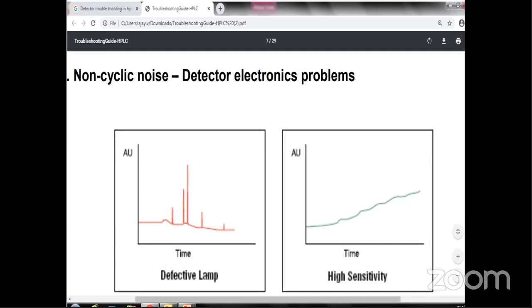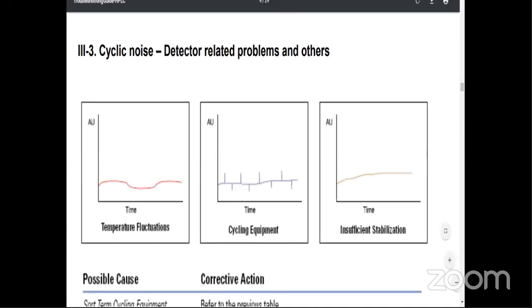And with high sensitivity, you can see there is a drift in the system showing up. If you're using a very highly sensitive detector, which makers are now providing, you may never have faced such challenges in other makes of HPLC, but particularly in these upcoming HPLCs you'll find these challenges appearing nowadays, because the sensitivity has tremendously increased for most HPLCs. Again, it's more or less the same slides, but you can see the temperature fluctuation, how it is reflected at periodic intervals. Then electronic spikes we have discussed, and insufficient stabilization, where I recommended that for isocratic methods we should equilibrate for a minimum of 30 minutes to 1 hour, or for gradient, you have to give a 3 cyclic gradient run, a blank run, to stabilize your systems.